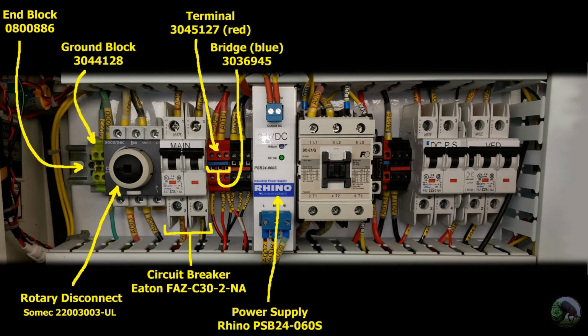Next up is this power supply. So this is a Rhino brand. I think that's the house brand for Automation Direct. And it's a little 60-watt DC power supply. So it takes 240-volt AC and makes a little bit of 24-volt DC. And that runs through the latching circuit, which is controlling this contactor, and going through the various e-stop switches. And so that's the next component, which is the contactor here. And this is a Fuji one. Once again, these tend to be rated by how much current they can interrupt. So you can just view it as a sort of big relay. So there's a 24-volt DC coil inside, and that's what's actuating whether this contactor is closed or open.